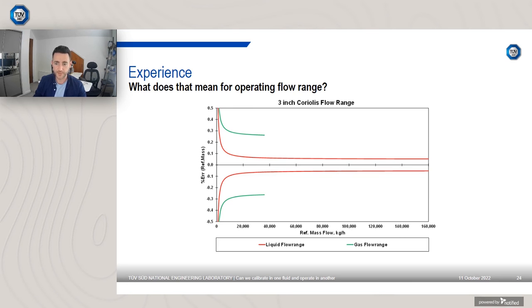What does that mean in terms of operating range? I've created a chart here with respect to that 3 inch Coriolis meter again. So remember, it's the same meter, it doesn't change whether you're using it in liquid or gas. It's the exact same device you will purchase, but it will have a different specification. I didn't include the specification I was going to, but a typical rule of thumb is a Coriolis meter for liquid has a mass flow specification of approximately 0.1. Some manufacture 0.05, but 0.1 is kind of in the range. And for gas, it's in the region of 0.35 to 0.5%, depending on the manufacturer. So for this manufacturer, you can see we're close to about the 0.3% for gas, and we're close to approximately 0.05 for the liquid flow rate. So a magnitude of a difference there between gas and liquid, but also I've overlapped the maximum flow rates.